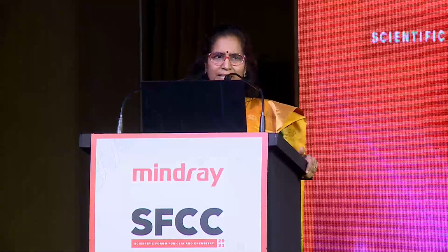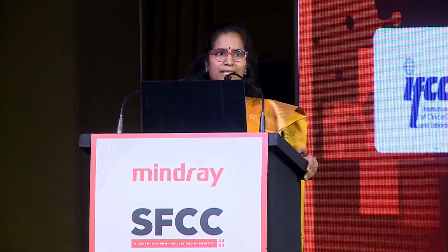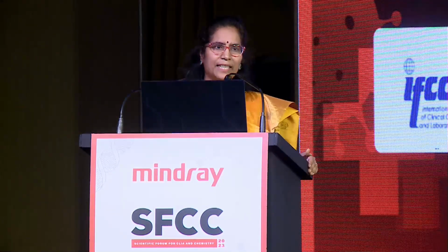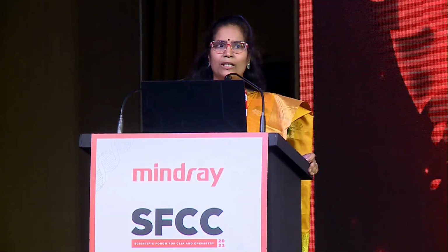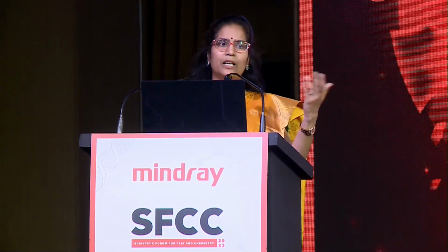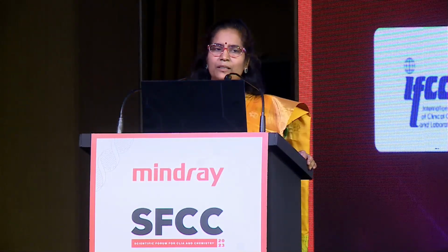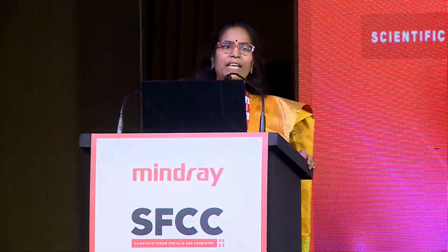Very true, sir. Only recently we received the Roche. Earlier we had the Siemens equipment. Definitely we still are in the process of harmonizing the equipment. But we have done that with the Mindray clinical chemistry analyzer. The reagents we used were not dedicated reagents. We used different reagents because it was an open system. Then it so happened that IQC was very good, but our EQA never was matching with the Biorad EQA result. So we had a factor.